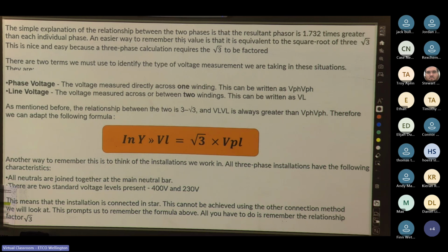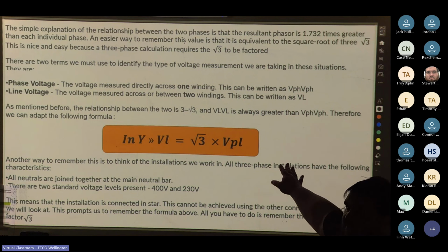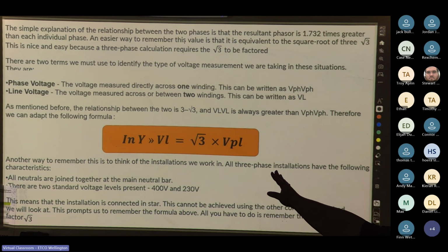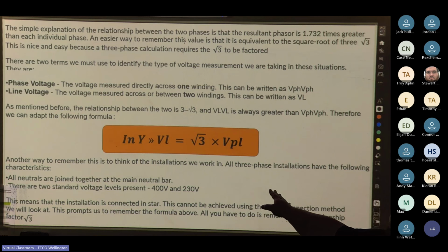Another way to think of this is the installations we work with. All three-phase installations have the following characteristics. All neutrals are joined together at the main neutral bar. There are two standard voltage levels, 400 and 230, which means that the installation is connected in star. This cannot be achieved using the other connection method we will look at. So always remember the above formula. In star, the voltage level changes between phase and line, and the relationship is always the square root of 3.